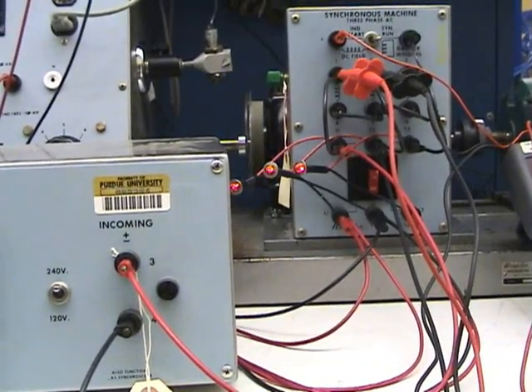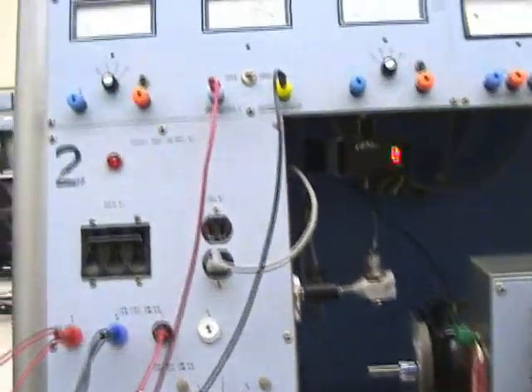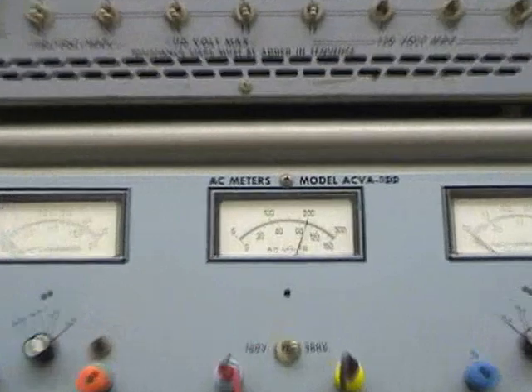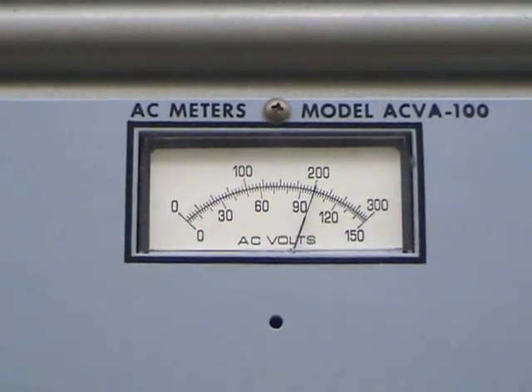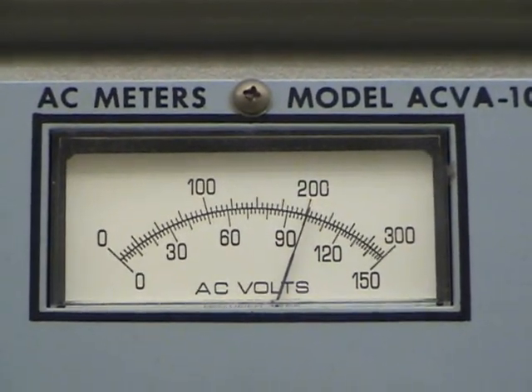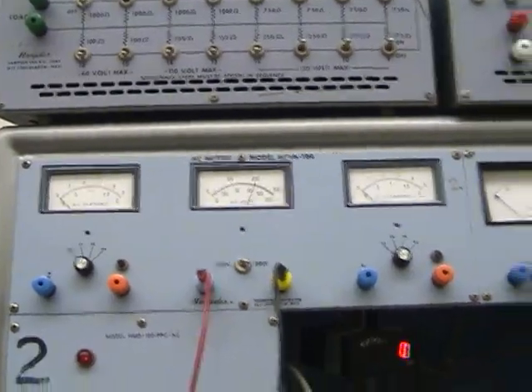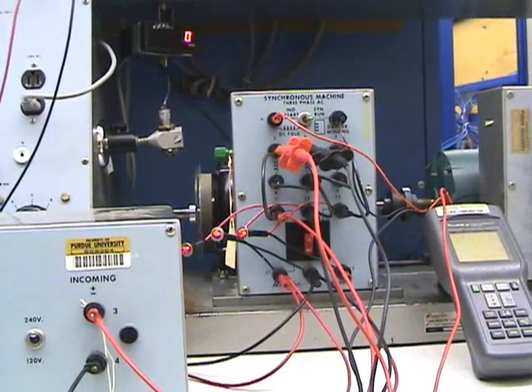The first thing we want to do is measure the line voltage for the power supply. And so looking at our meter up here, make sure you're set on the high scale here, and we can see that we're right at 200 volts line voltage here. That'll be important because we want to make sure that the generator is putting out 200 volts as well, so that when we close the switch, there's not much voltage across the switch.